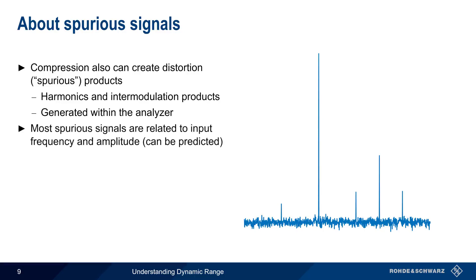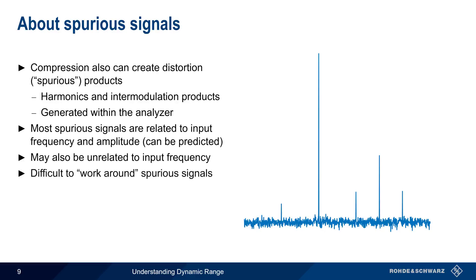In addition to causing inaccurate amplitude measurements, compression can also create distortion or spurious products. These include both harmonics and intermodulation products, which are generated within the analyzer itself and which are not present in the input signal. The frequencies of both harmonics and intermodulation products are usually related to the frequency and amplitude of the input signal or signals, and thus can be predicted. In some cases, however, spurious signals may also be unrelated to input signal frequency, and may appear on the analyzer display even when no input signal is present. Generally speaking, spurious signals are difficult to filter out or otherwise work around, and thus the presence of spurious signals limits the range over which we can accurately or reliably measure signals.